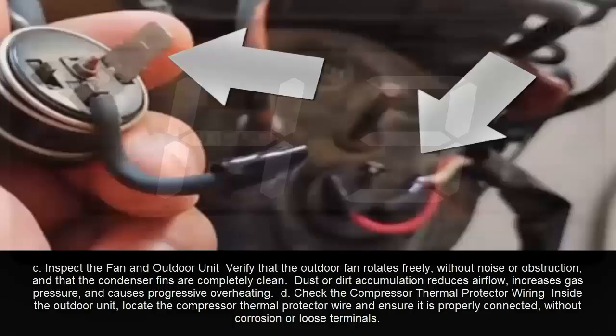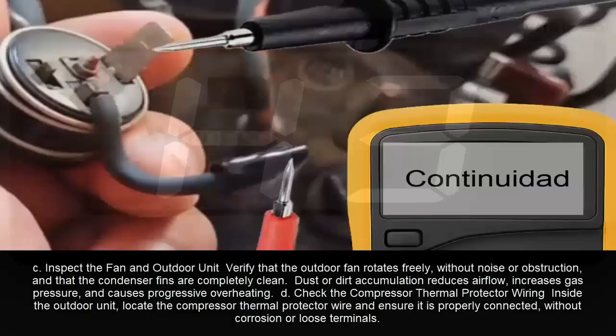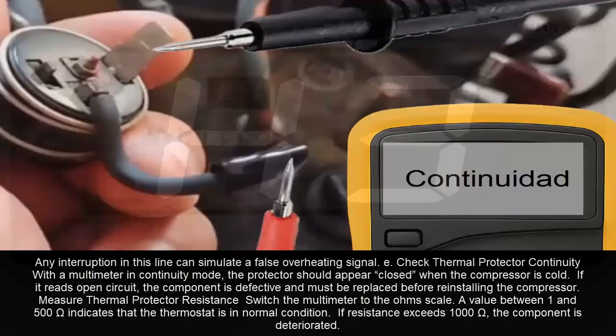D. Check the compressor thermal protector wiring. Inside the outdoor unit, locate the compressor thermal protector wire and ensure that it is properly connected without corrosion or loose terminals. Any interruption in this line can simulate a false overheating signal.